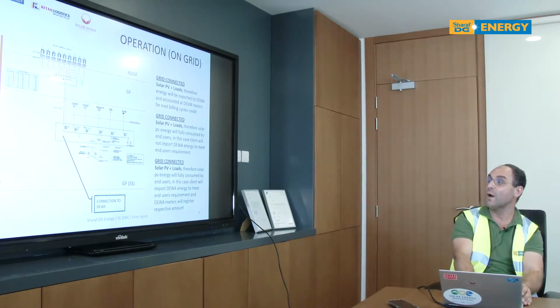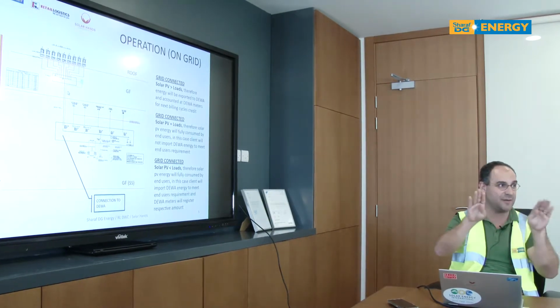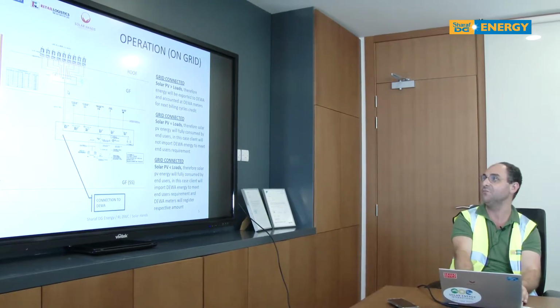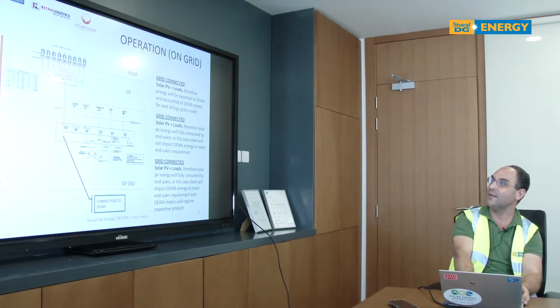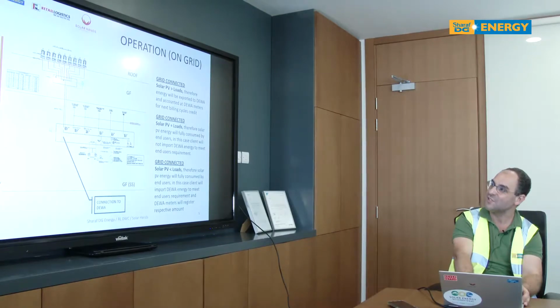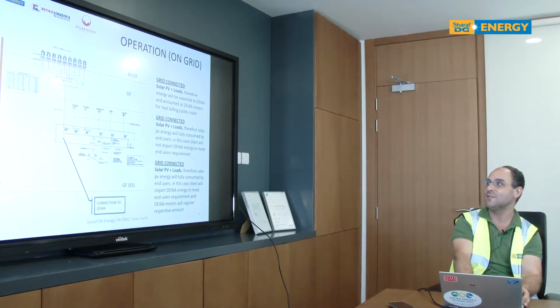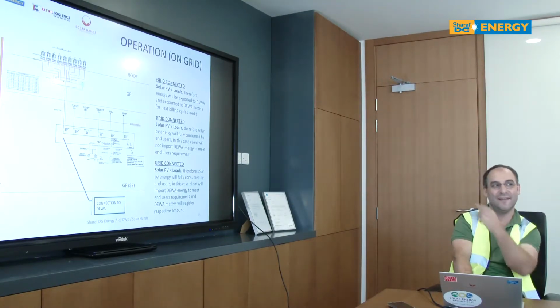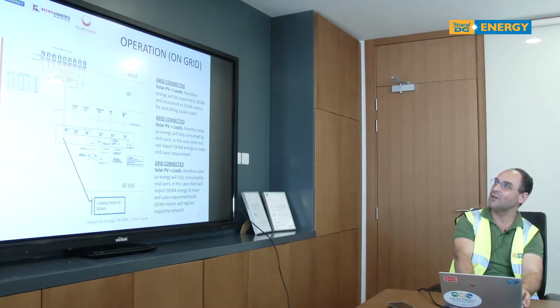So this line should be above. This is only for one of your systems. Since you have two separate systems, you have two SLDs, right? Then you have that combination box. This is your facility already. This is your LV panel 2 in the substation. So what we are doing is combining all the outgoings of these inverters, bringing it here, and delivering to the same panel.